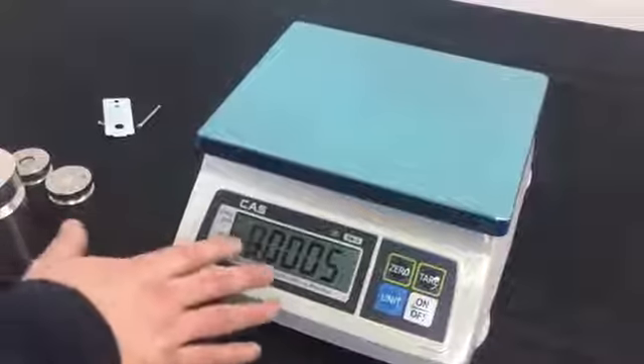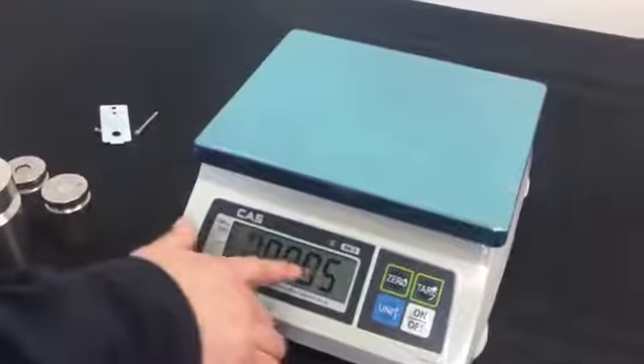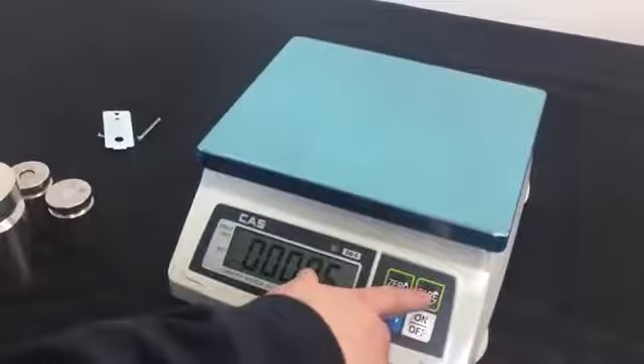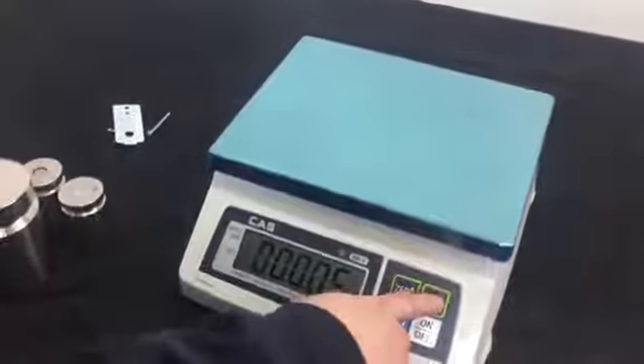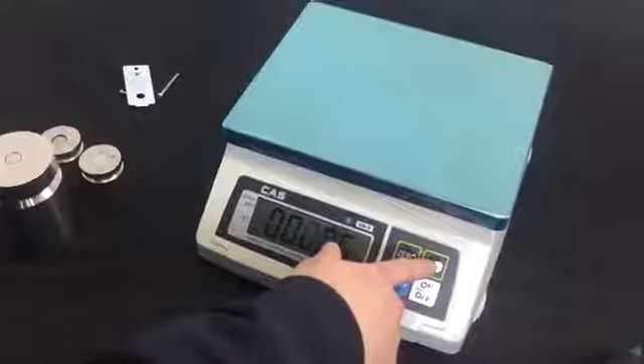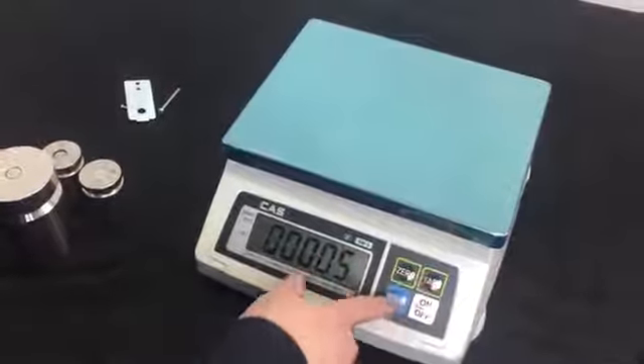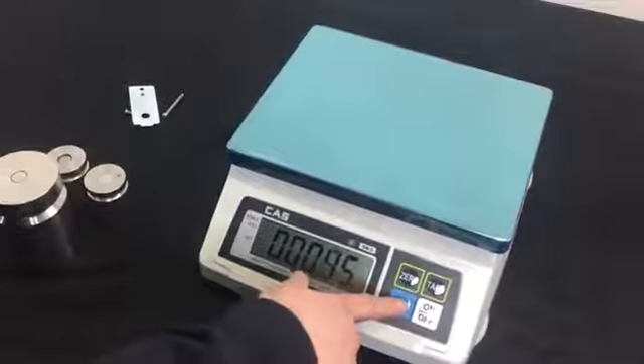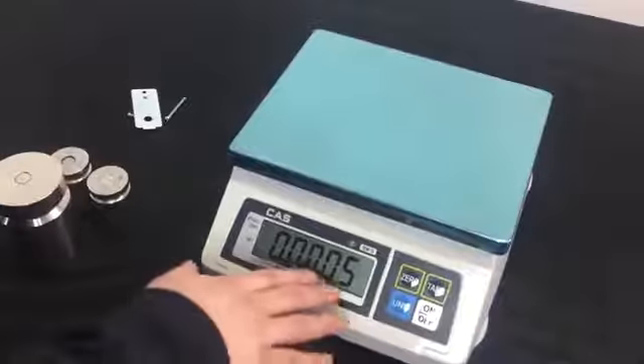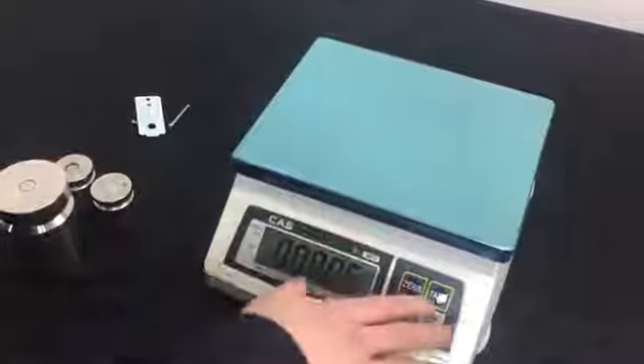Now you press the 0 key. It says capacity. This is flashing zeros and then 5. If you wanted to change this number, you would just use the Tare key to move to the right. And if you wanted to change the number, you would use the unit key in order to change that number. We want to keep it at 5. That is our capacity with the scale we're working with today. So let's press the 0 key.